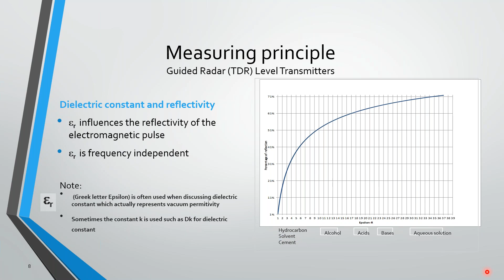Dielectric constant is simply a number - there's no actual engineering unit for it. Looking at a range of products from hydrocarbons to aqueous solutions, the percentage of reflection goes up with increasing dielectric constant. With an aqueous solution, we see a lot of reflectivity - pretty easy to measure. As we get down toward hydrocarbons, it becomes more difficult to measure with a radar level device - doesn't mean we can't, just that it's harder. In some cases, if the dielectric is way too low, we simply cannot use this technology.